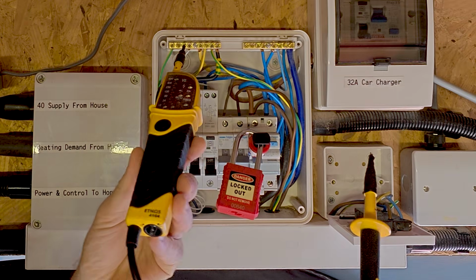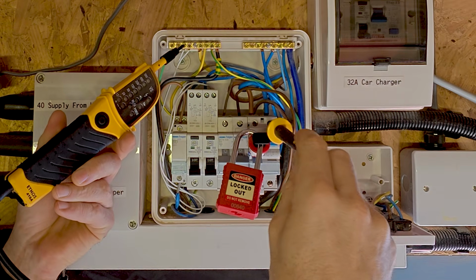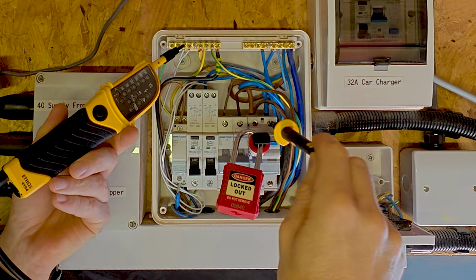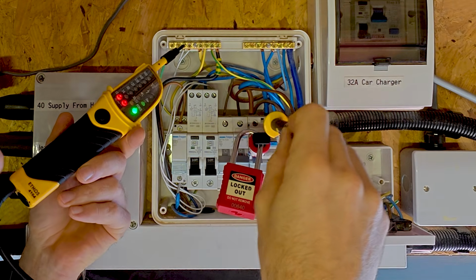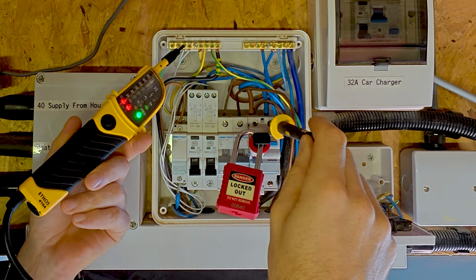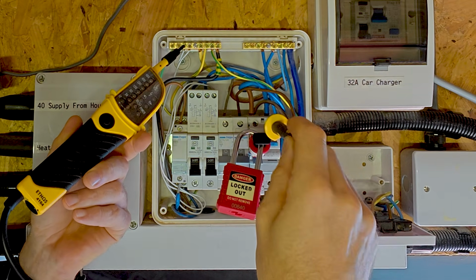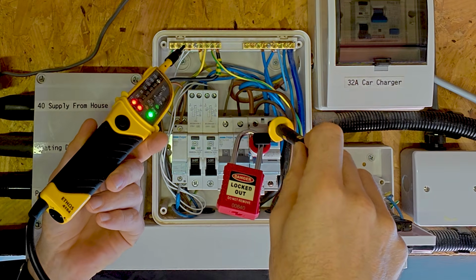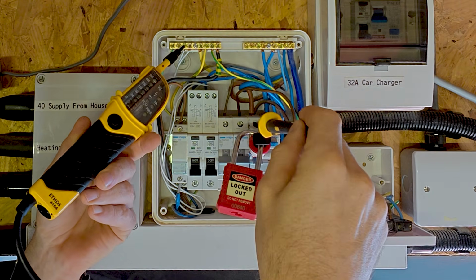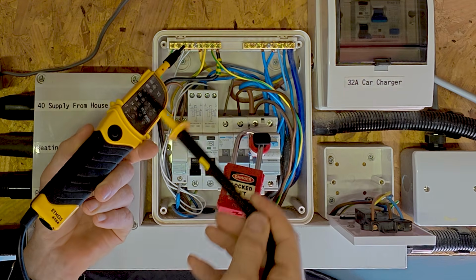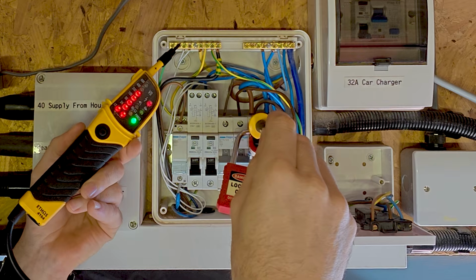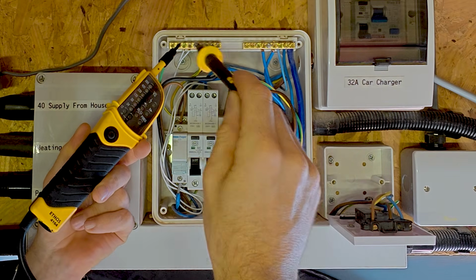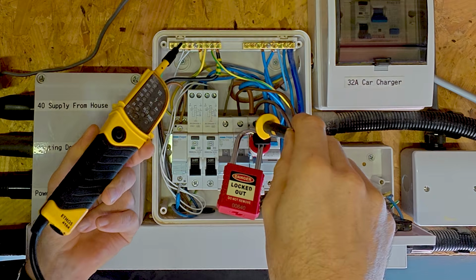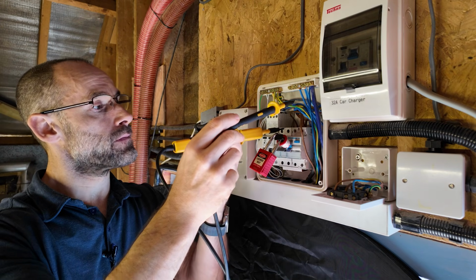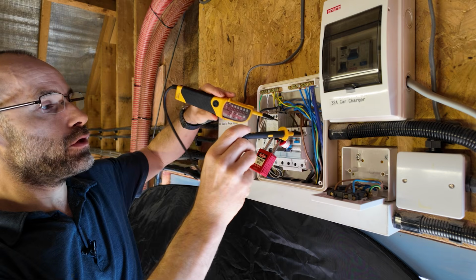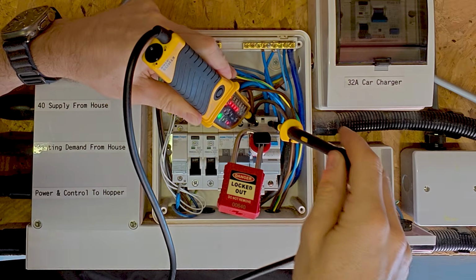So if we were to go between the ground or earth or CPC and the neutral, you would expect no voltage, and there's no stack of lights here, and you might have continuity for reasons to do with your earthing arrangement I won't bore you with now. So this is what I want to see. There's no voltage between neutral and earth. Yeah, they should be at about the same voltage. Right. Now, if I go between earth and line, I should see a stack of voltage lights. You see that stack of lights light up there? And that's going up to 230. So that is showing that between earth and line, you're getting 230 volts. That's what you'd expect. This is the one you don't want to touch. And the final check is when you go from line to neutral, like so, you should also see 230 volts.